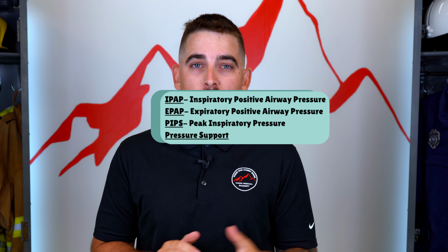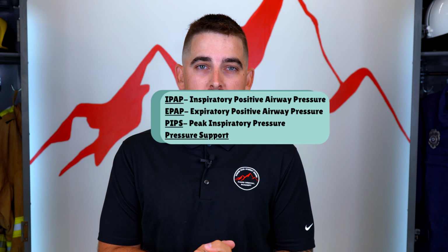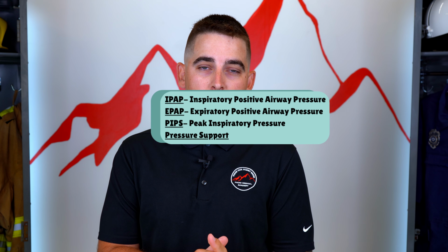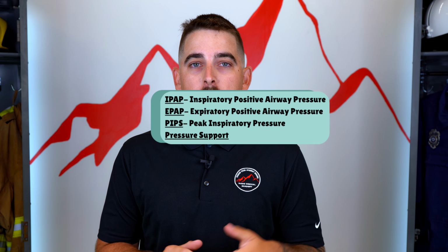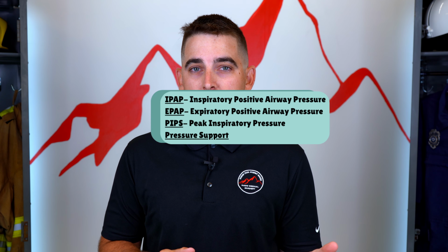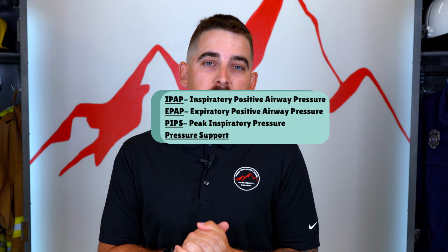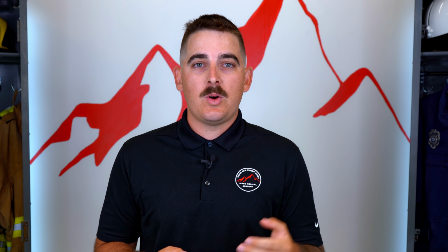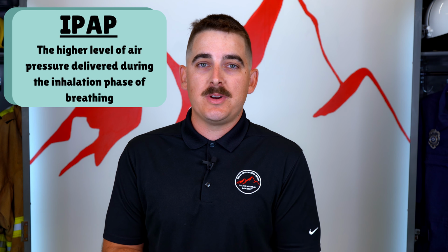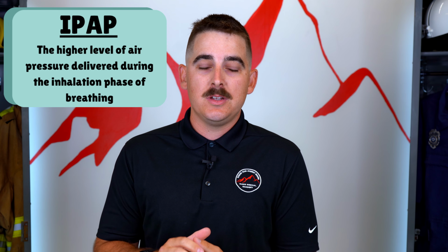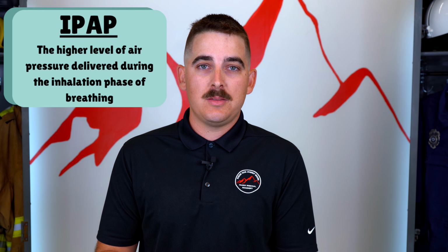Let's break down some terminology for bilevel positive airway pressure. Some terms that we need to know are IPAP, or inspiratory positive airway pressure, EPAP, or expiratory positive airway pressure, peak inspiratory pressure, or PIP, and pressure support. IPAP, or inspiratory positive airway pressure, is the pressure delivered when the patient takes a breath in during the inhalation phase.